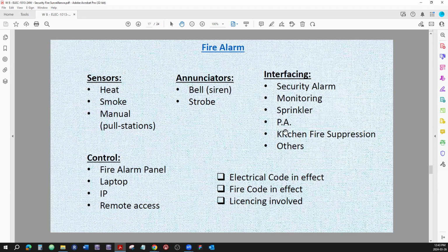All right, so also things are interfaced with the PA systems because you need to have some annunciations going on. Kitchen and fire suppression systems. Commercial kitchens do have fire suppression systems. There are nozzles above the stove, and it's connected to what's called the extinguisher bottle, somewhere in the wall or close by, and it's connected through a bunch of pipes and sensors. And above the stove, there will be heat sensors. If the heat goes up by a certain amount so that it's actually detecting fire, then the whole thing triggers and the stove is extinguished by those nozzles on top of it, right?